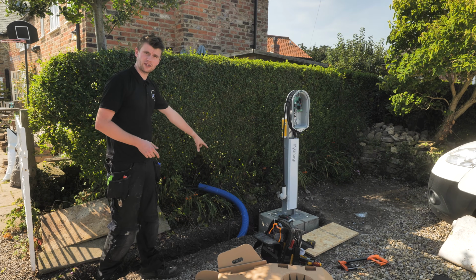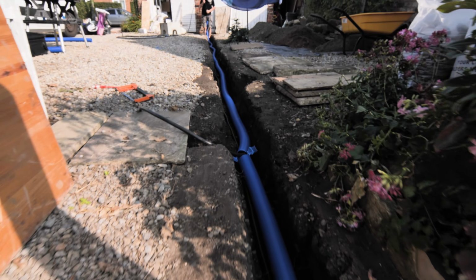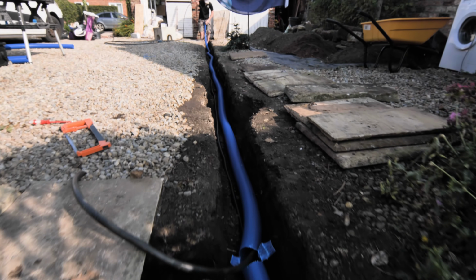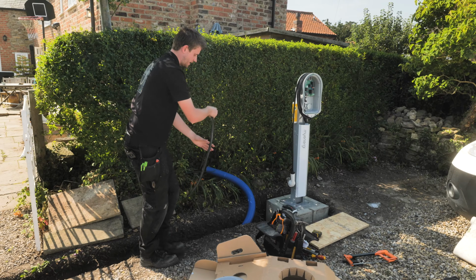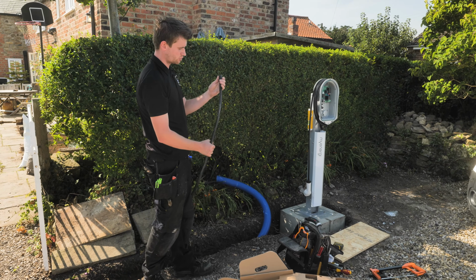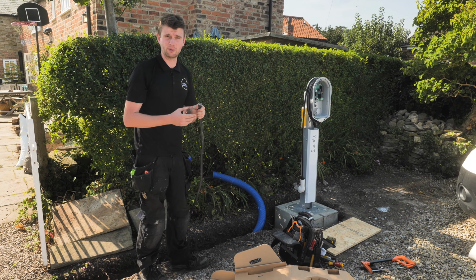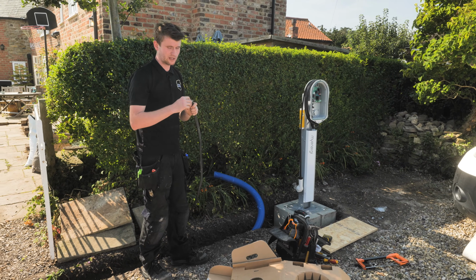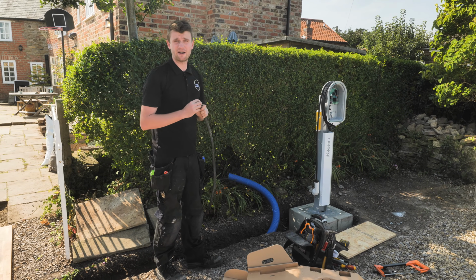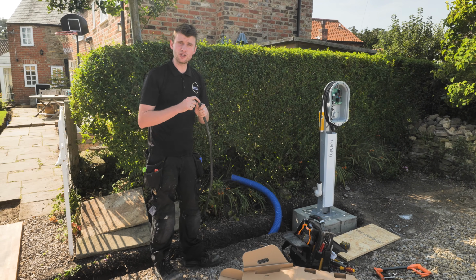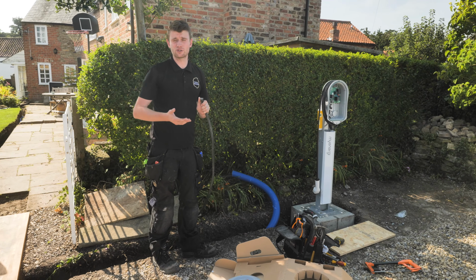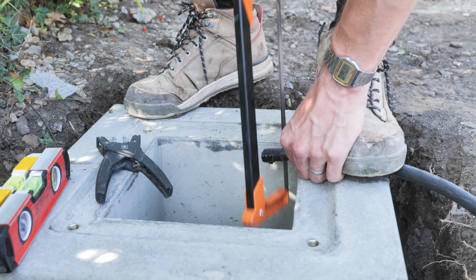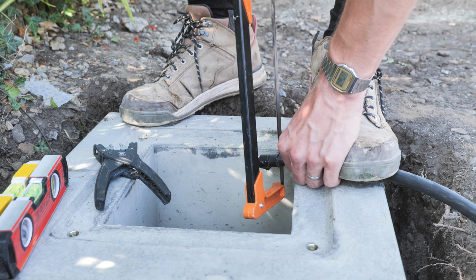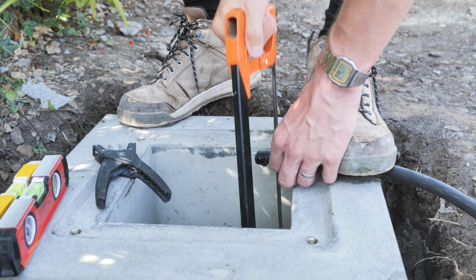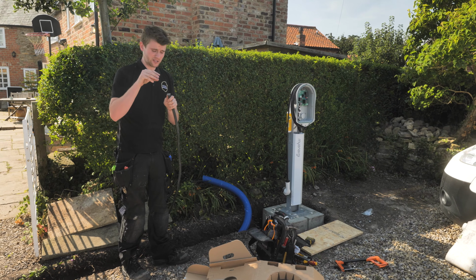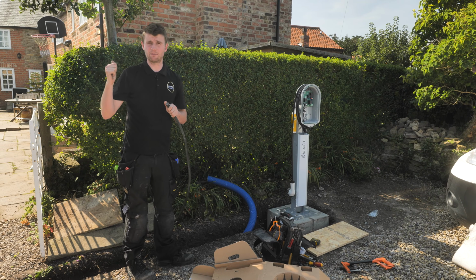You can see here we've got the blue ducting, so that comes up, and this one comes from the garage. That has got the Doncaster cable EV Ultra SWA, so it's still an armoured cable, and it's got a 6mm live, neutral and earth, and then a Cat 5 cable built within it. The reason we're using that is it's an armoured cable, so it's a lot better to go in the ground, protected by the armouring, but it's also got this Cat 5 cable in, which will allow us to connect hardwire.